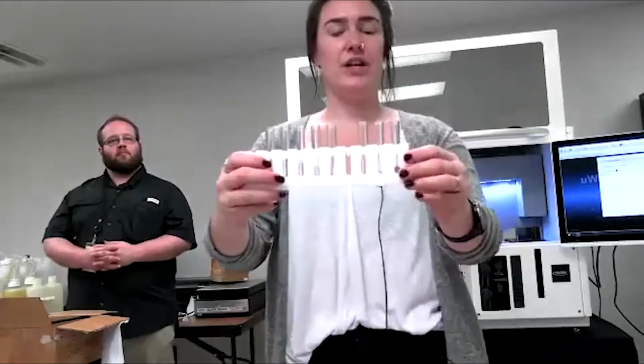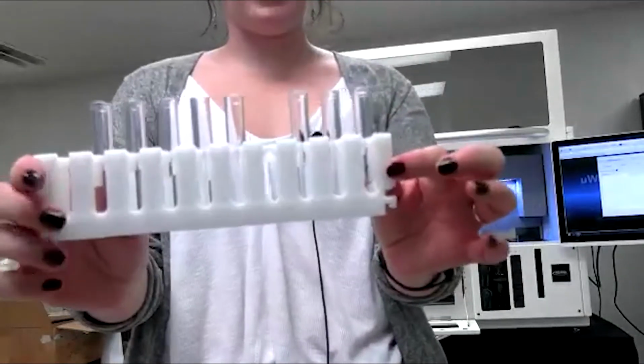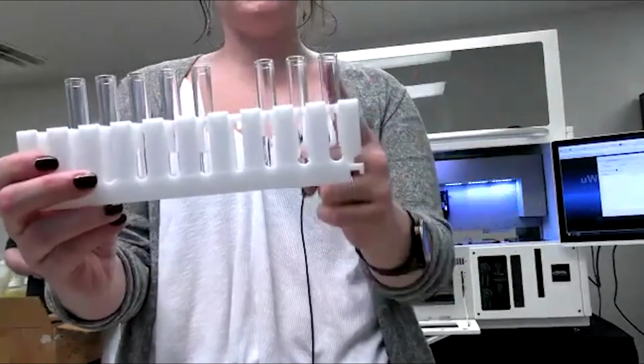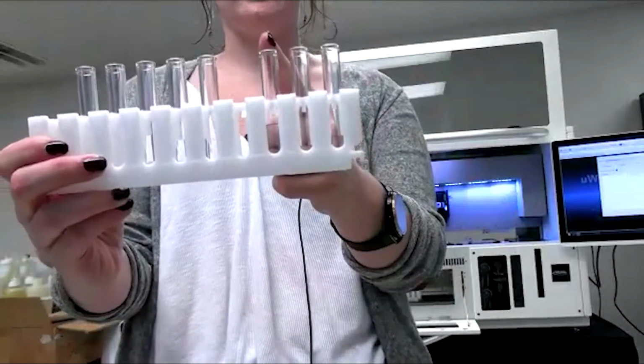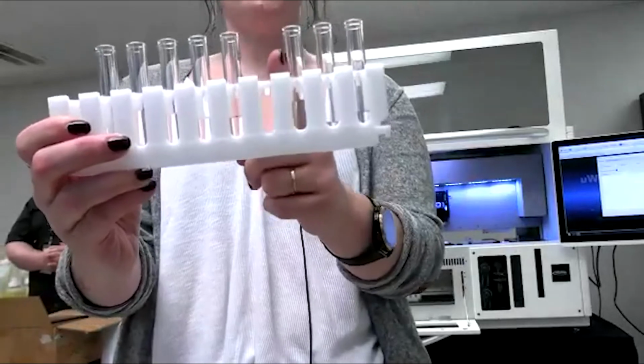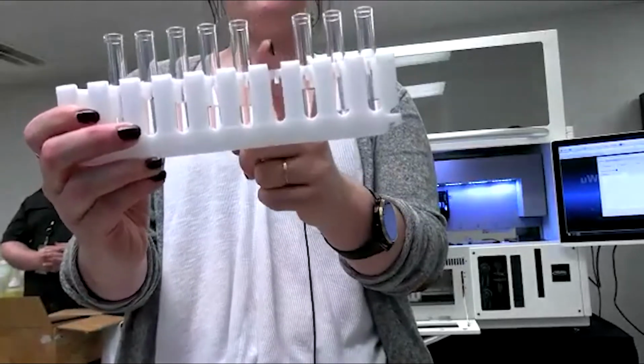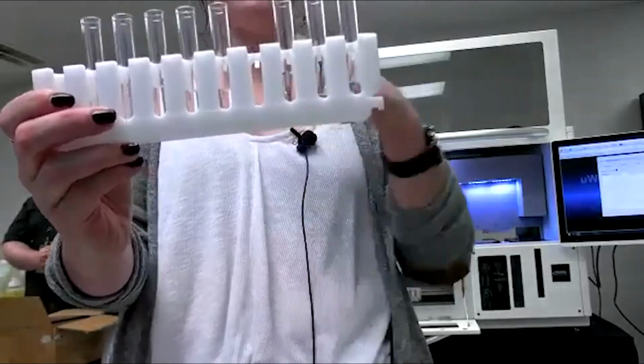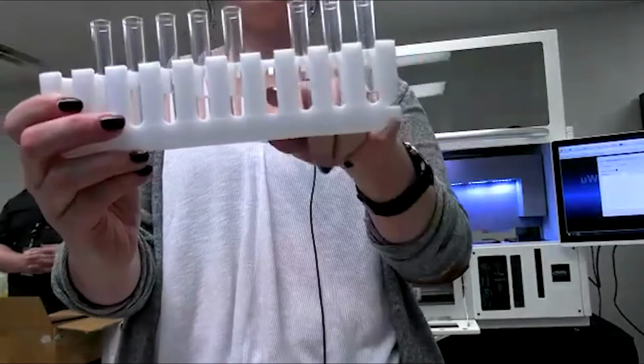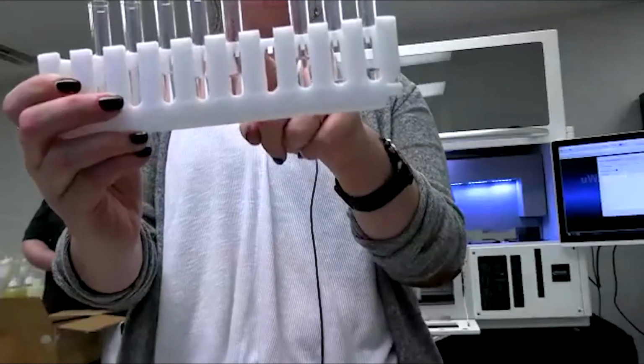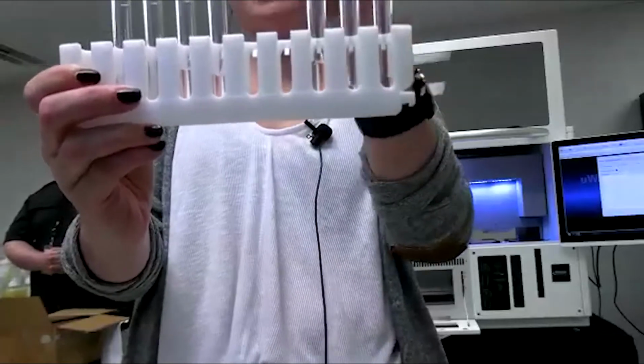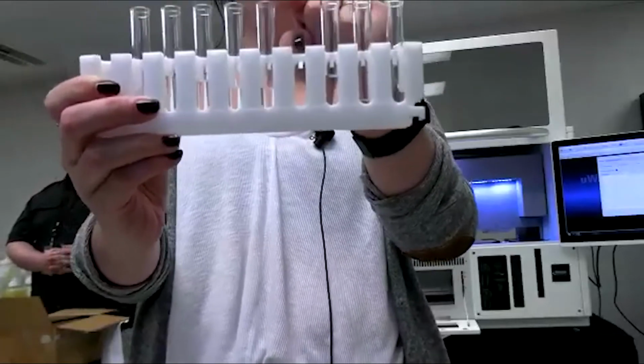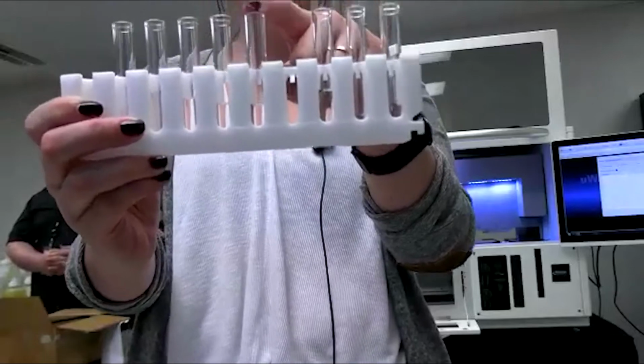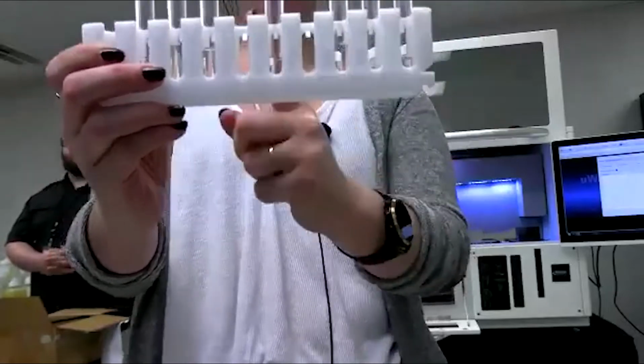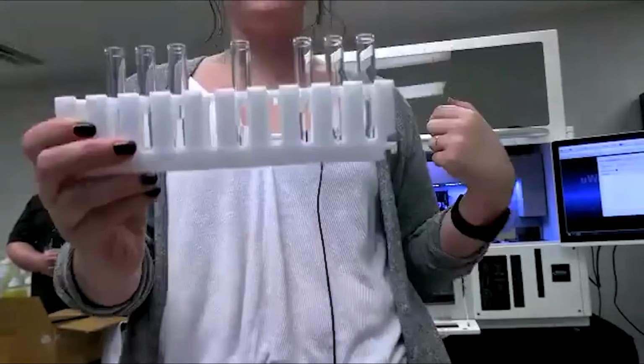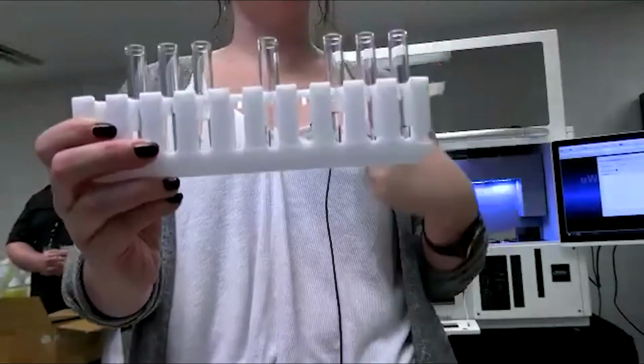So if this was the sample rack that I was using, it would start at this end, it would sample from here, here, here. It would see that there is no tube here. So it would both skip this tube and it would also skip the sample 4 position on your tray. And then it would move to the next tube to sample. Even if this tube was empty, it will see that there is a tube and try to sample there. But if there is no tube, it will skip over that position and the corresponding position on your sample tray.